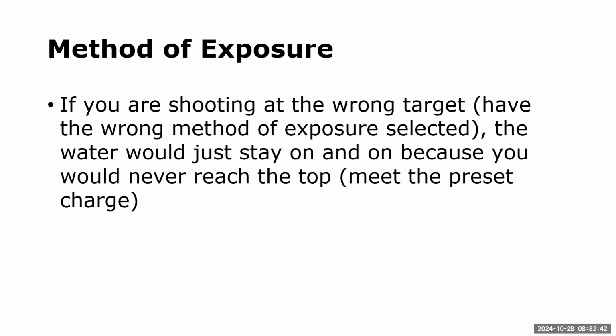So here it would be like if I'm supposed to be shooting at Cody, because that's my target, but I'm shooting over here at Emma. Is this ever going to fill up over here if that's the photocell that I have selected? No, because I'm shooting over this way. So this is the same thing. If I am directing my beam down at the table, but I have wall bucky selected, are those buckets over there going to fill up? Nope, it's just going to stay on and on and on.